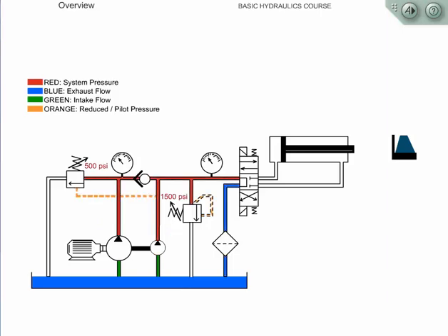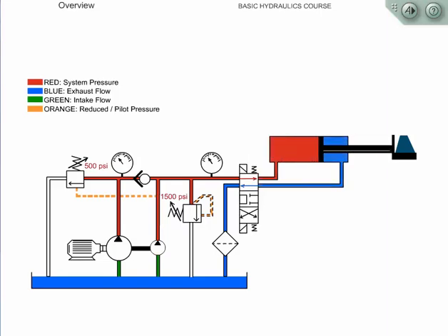As the cylinder approaches the load, the pressure requirement is low. If the pressure requirement is below the unloading valve setting, both pumps work together to provide a rapid approach to the load. At this point, the system pressure increases, thereby opening the unloading valve. The flow from the high-volume pump is directed back to the tank at a minimal pressure.